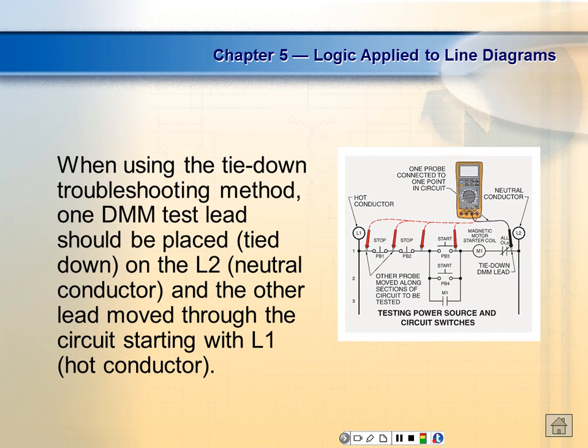This is what we're talking about with troubleshooting. Normally if something's not working, it's either not getting voltage or it's actually defective. It's getting voltage to develop power, but the device itself is defective. So it means we've got an open circuit somewhere. If we've got an open circuit, we don't have work. But what's nice is that the total voltage will be dropped across the open, because nothing else is dropping voltage anymore, right?